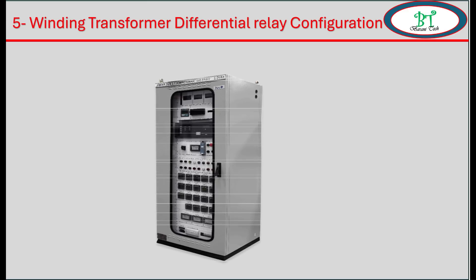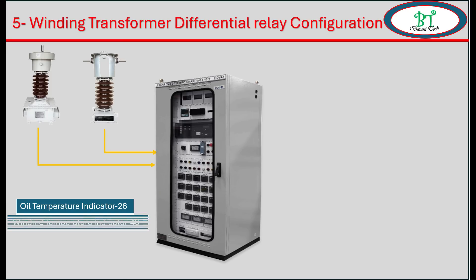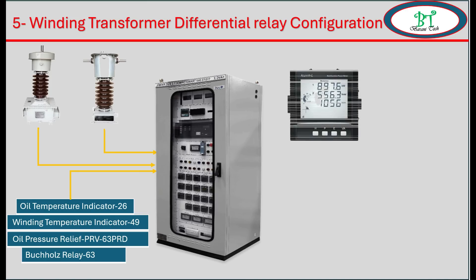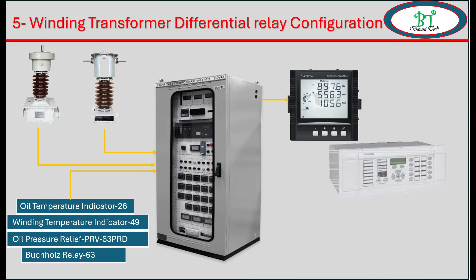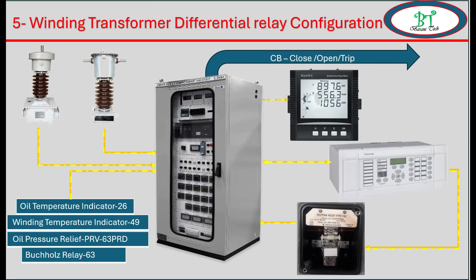From the CT, VT, and transformer protection signals — such as transformer temperature, transformer oil pressure, and Buchholz relay — all are connected to this control panel. Trips and alarms are associated with tripping and annunciation. We also have the energy meter, numerical relay, and master trip. With the numerical relay and master trip, the tripping to the breaker is configured via software and hardware.